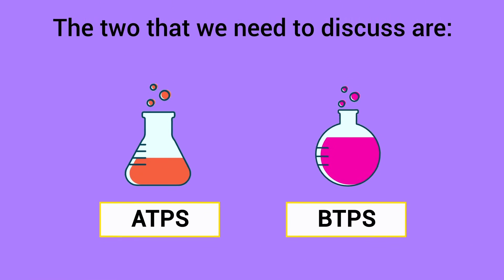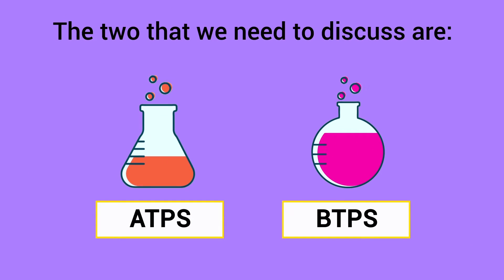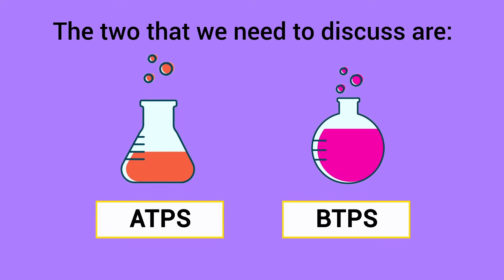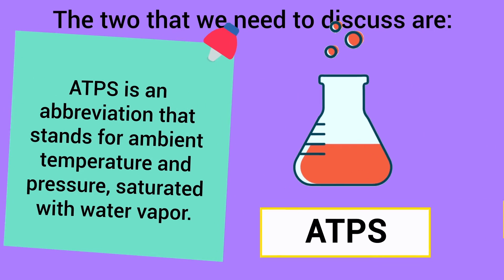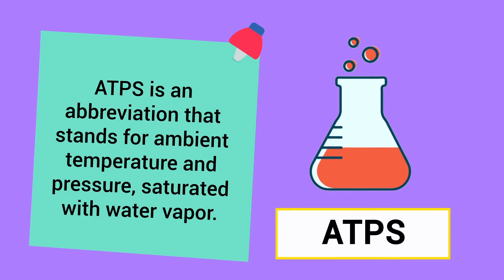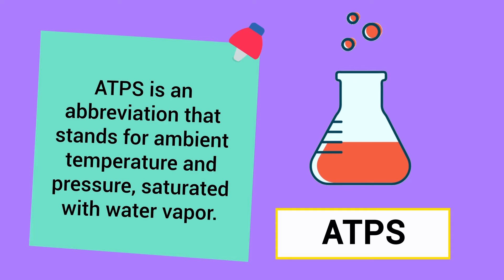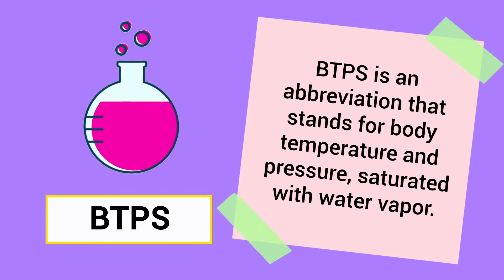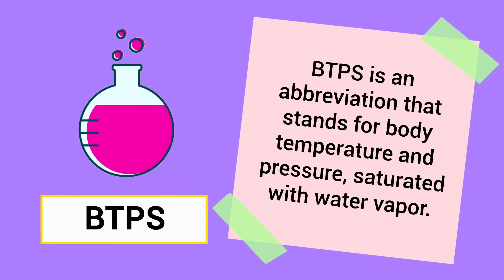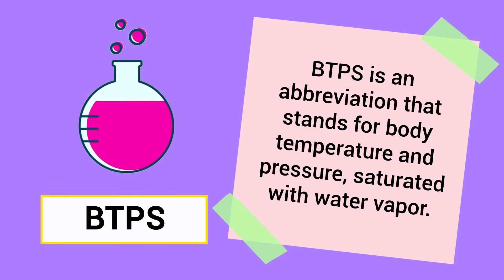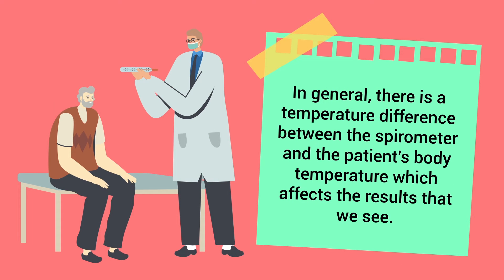The two that we need to discuss are ATPS and BTPS. ATPS is an abbreviation that stands for ambient temperature and pressure saturated with water vapor. BTPS is an abbreviation that stands for body temperature and pressure saturated with water vapor. In general, there is a temperature difference between the spirometer and the patient's body temperature, which affects the results that we see.